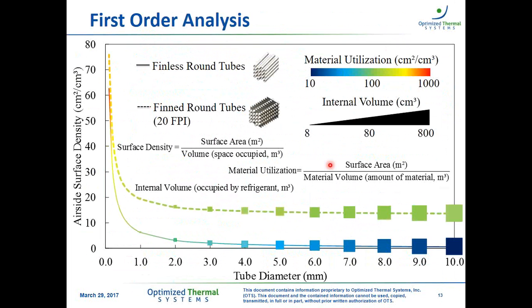And the third one is the internal volume. The internal volume indicates the amount of refrigerant that we will have in the heat exchanger. What we're seeing on the x-axis is the tube diameter, and the two curves here are for finless and fin tubes. The purpose is not to compare one and the other, but how they change with respect to the three metrics described above. So we can clearly see an increase in compactness as we reduce the tube diameter, and obviously a very steep increase as we go below 1 millimeter.